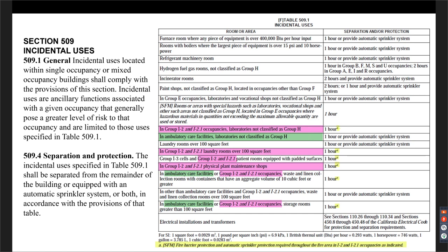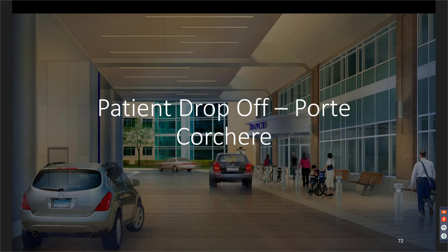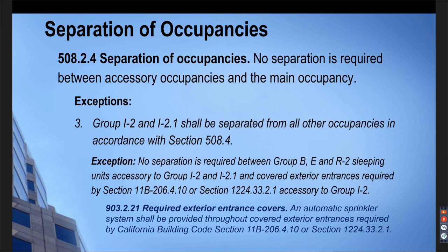Patient drop-off areas, there you'll see in chapter 5, there's 508, that's part of the code that helps you determine, do I need separation between these mixed uses? Is it non-separated? Is it accessory? And 508.2.4 is under the accessory portion of 508 and indicates that you do not need separation between accessory occupancies and that main occupancy, and then has some exceptions. For an I-2.1, it doesn't make sense at first because the charging section says, hey, you don't need a separation if it's accessory between the main and accessory.